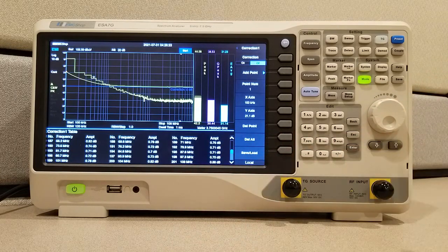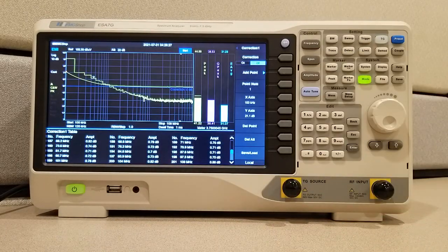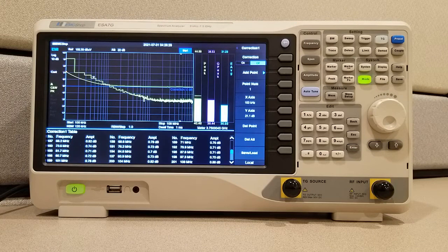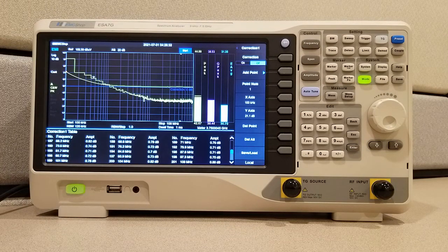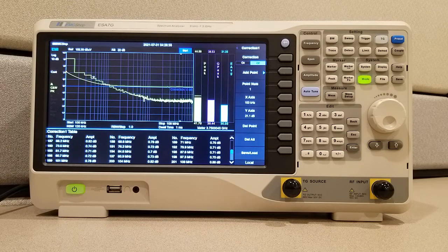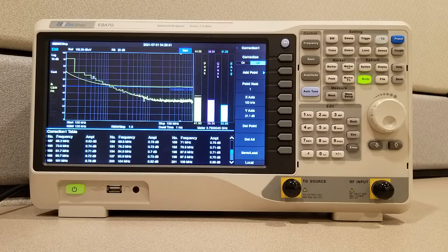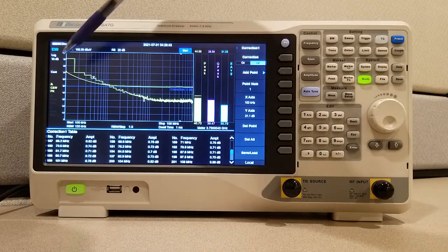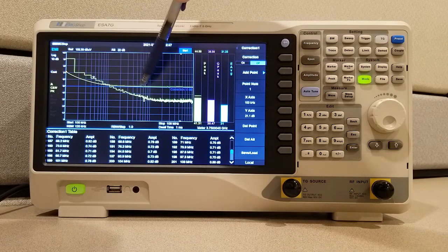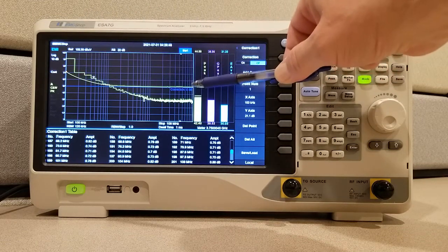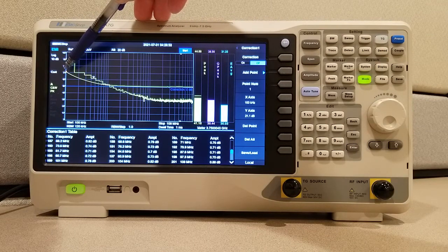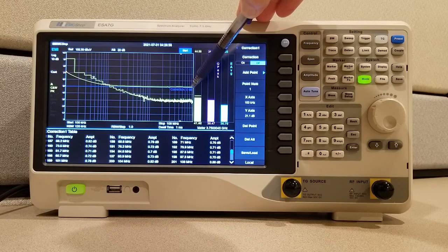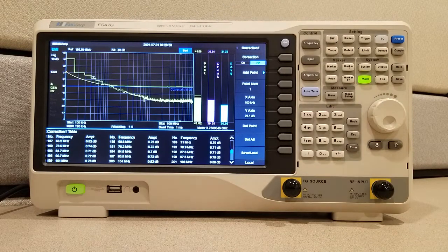You will see that these numbers are positive. So when you're putting in a correction value that is a loss, you will be, for this software, putting it in as a positive value. If you're putting in a correction that is a gain, you will be putting that as a negative value. Another thing you will see is a representation of what the correction file is giving you here. You see that there's a lot of loss at the lower frequencies, and hardly any loss, almost zero, at the higher frequencies.